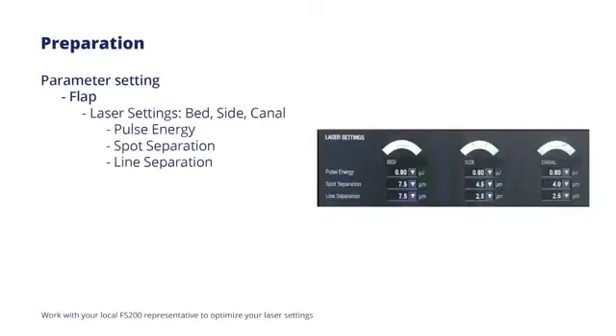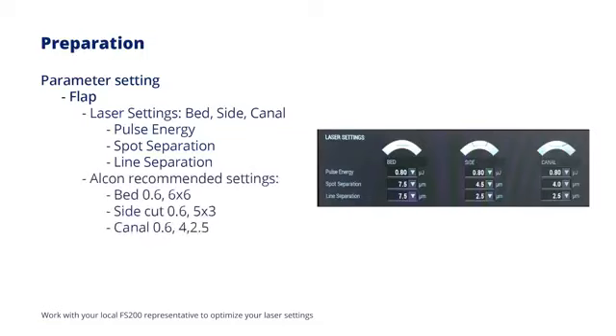Laser settings for flap creation in bed, side cut, and canal can be adjusted for optimization of pulse energy, line and spot separation, according to individual machines or surgeon's preference. As shown here are Alcon recommended settings, and ours in the lighter color.